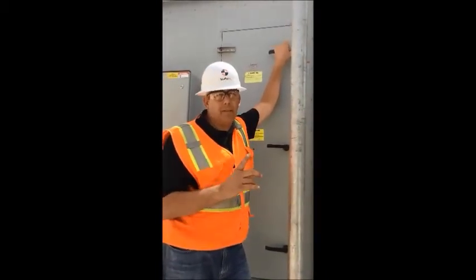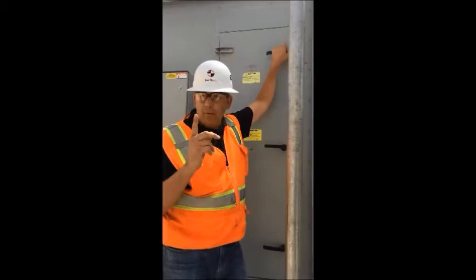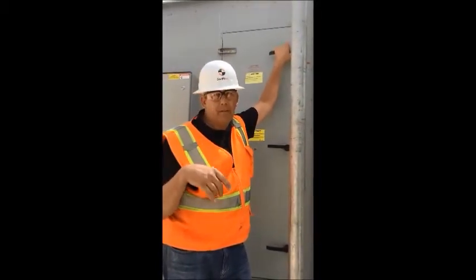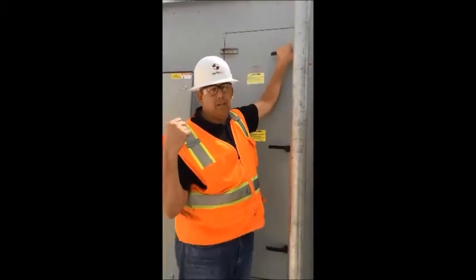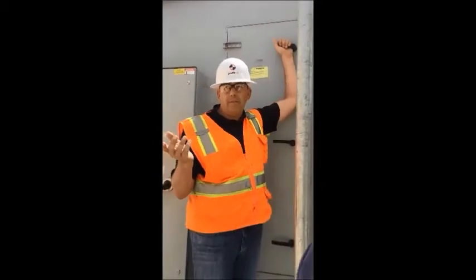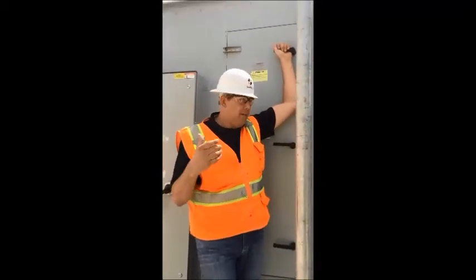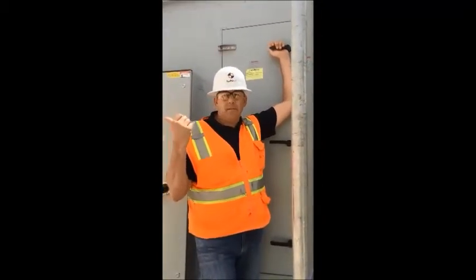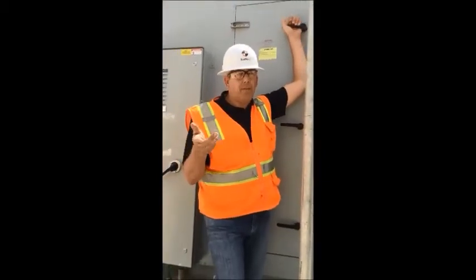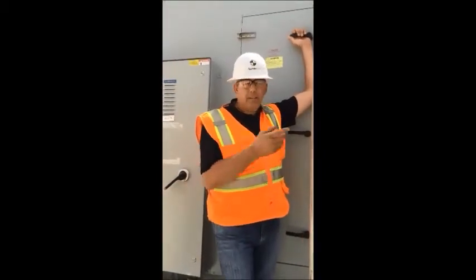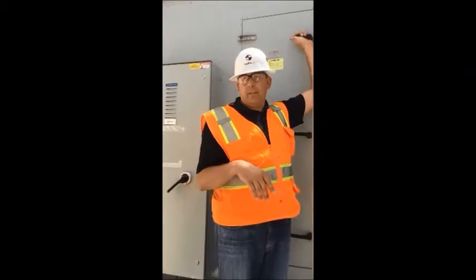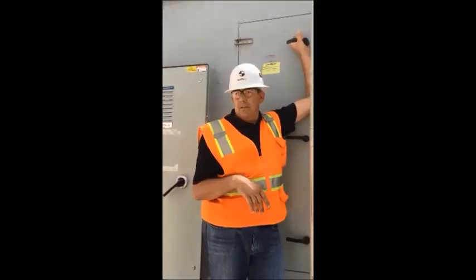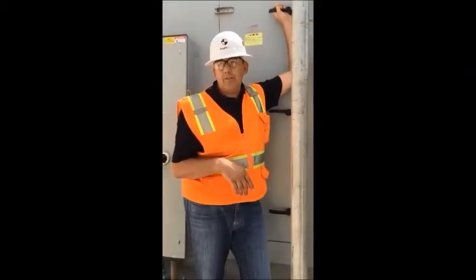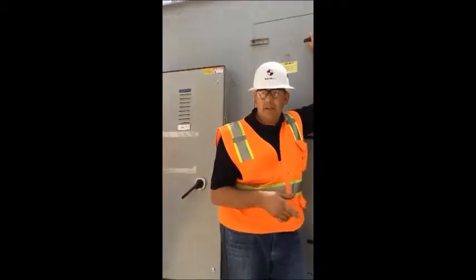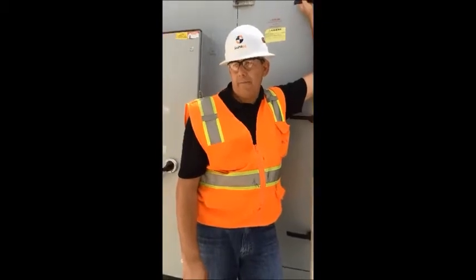Okay, that's the number one thing about this. Actually, number 2 thing. Number 1 thing is obviously don't get in the VFD cabinet when it's hot. Obviously, you have to use your own lockout tagout procedures that you have here for the campus, but there's labels on the units, making sure that you don't get in them, but obviously you have your own protocol. But again, these UV lights will burn your skin, they'll burn your eyes. So make sure that when you're working in the cabinet, again, that you leave the door open and make sure they're off.